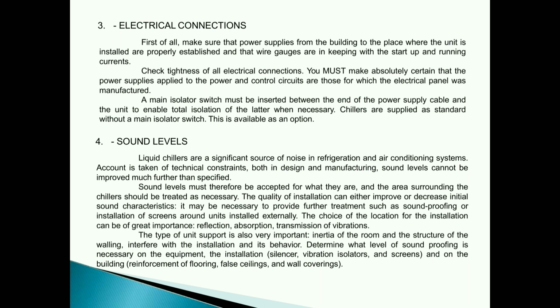4. Sound levels. Liquid chillers are a significant source of noise in refrigeration and air conditioning systems. Account is taken of technical constraints, both in design and manufacturing. Sound levels cannot be improved much further than specified. Sound levels must therefore be accepted for what they are, and the area surrounding the chillers should be treated as necessary. The quality of installation can either improve or decrease initial sound characteristics.